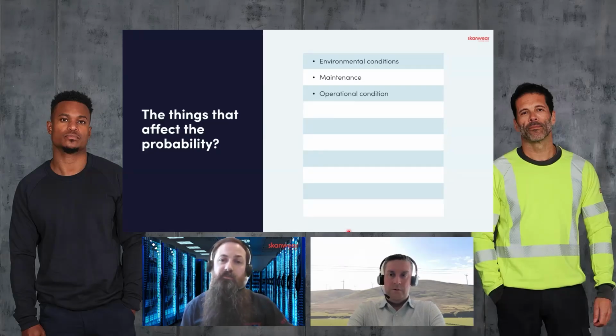Maintenance and the condition of the equipment is a massive consideration affecting the probability of an issue. Consider the operational condition too: how long has a circuit breaker been in the same position? If it's been closed for years without cycling, it may have worked at last maintenance but might not operate as expected in the event of a fault.